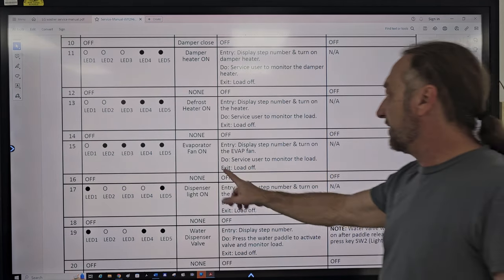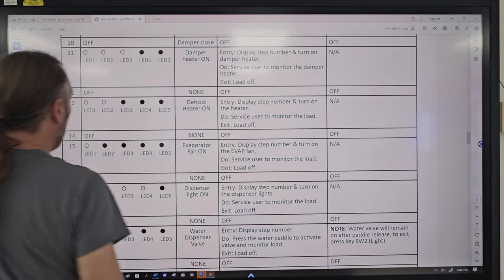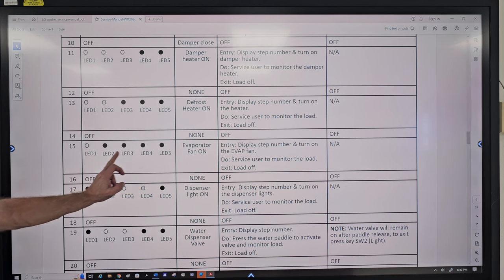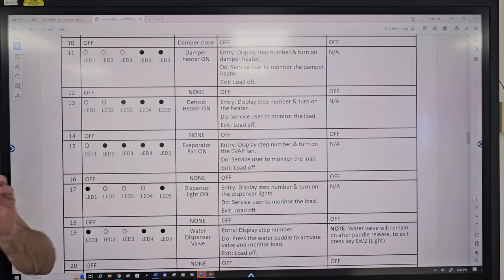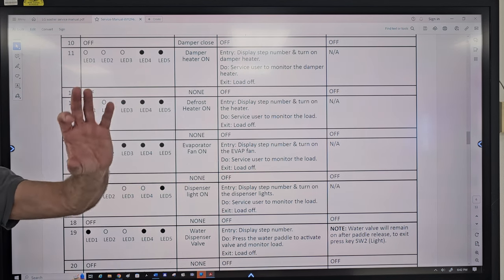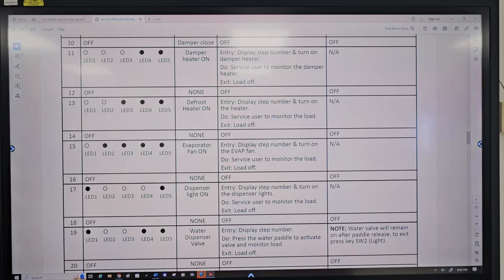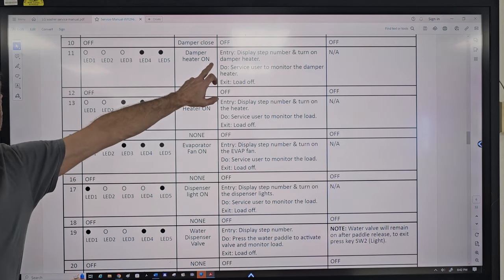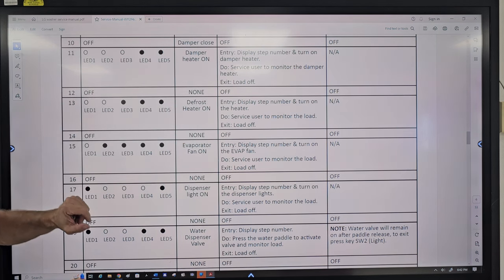Step 15 says evaporator fan on. Now you have to look at these LEDs, depending on what light is lit on your display, that tells you what mode or step you're in. Notice that if just these three lights are on, it's defrost heater. If just these two are on, that's the damper heater, a heater on the damper.